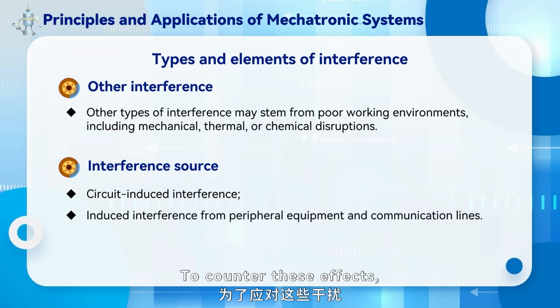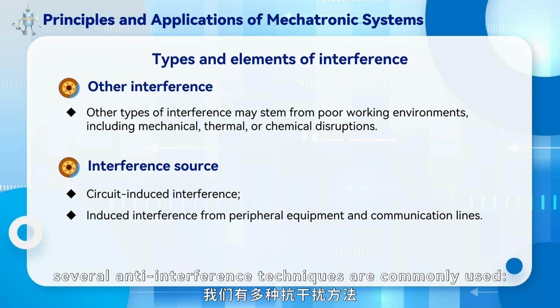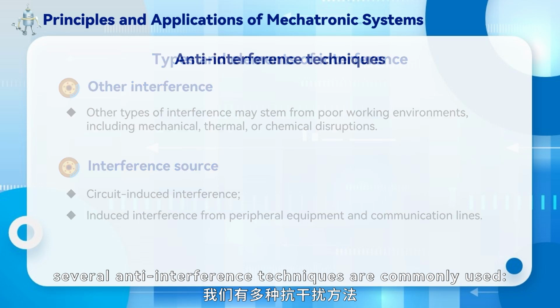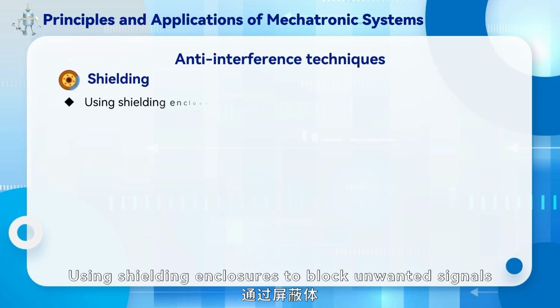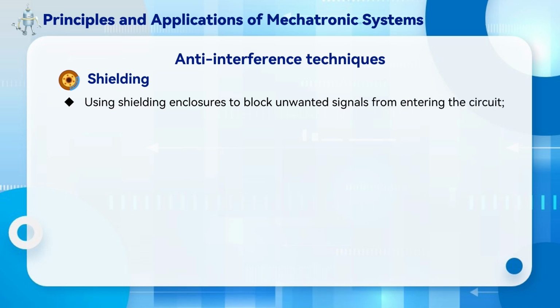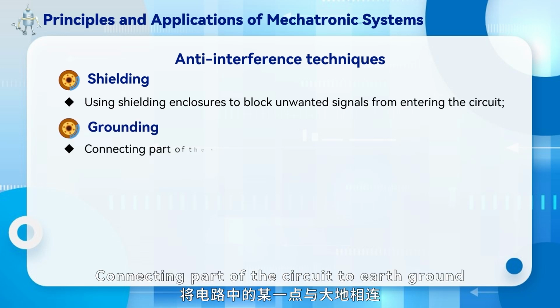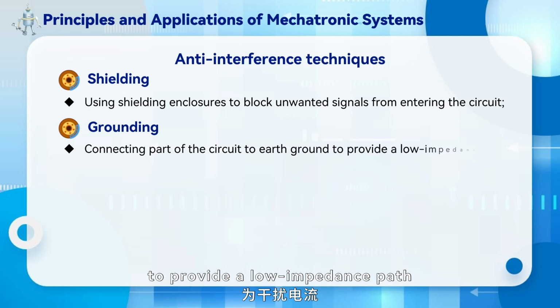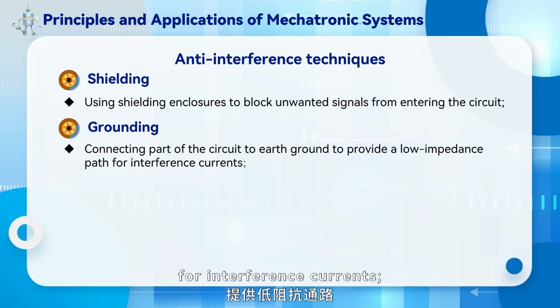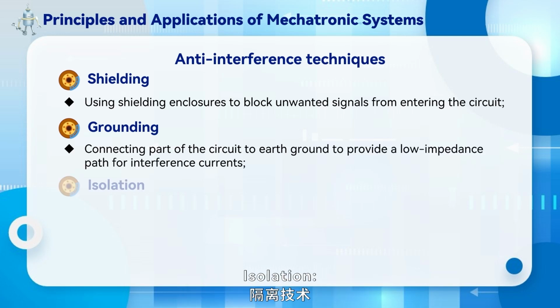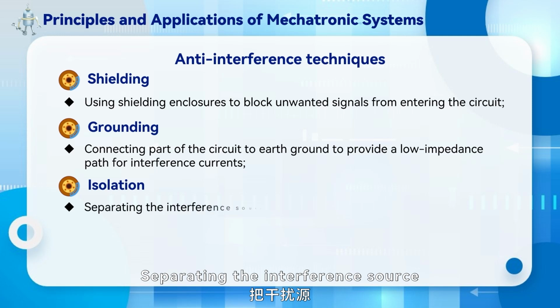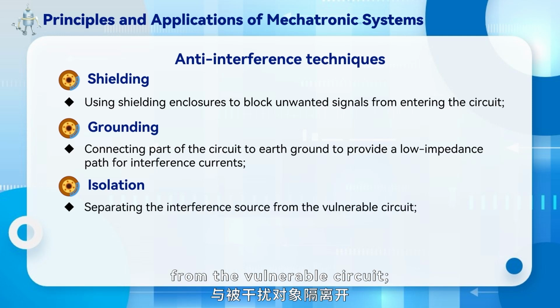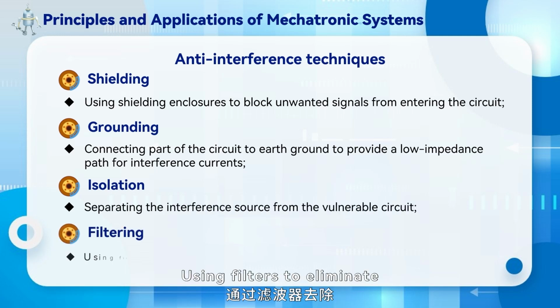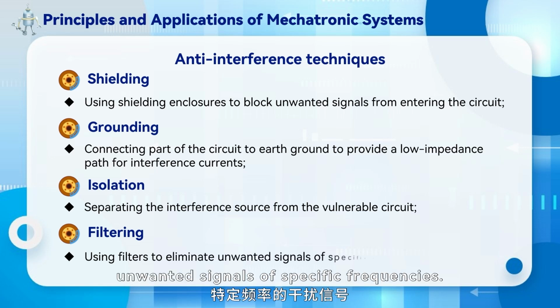To counter these effects, several anti-interference techniques are commonly used. Shielding, using shielding enclosures to block unwanted signals from entering the circuit. Grounding, connecting part of the circuit to earth ground to provide a low impedance path for interference currents. Isolation, separating the interference source from the vulnerable circuit. Filtering, using filters to eliminate unwanted signals of specific frequencies.